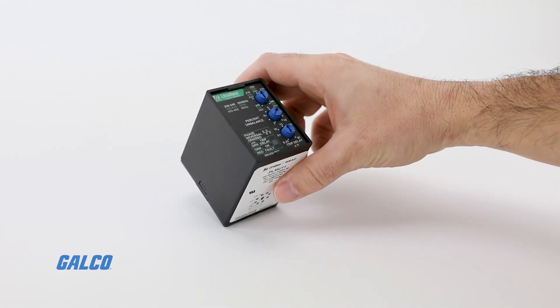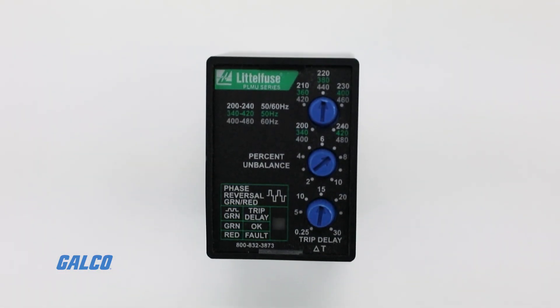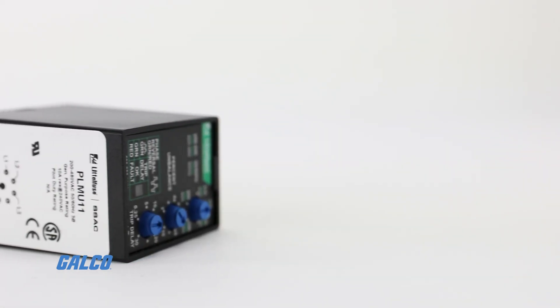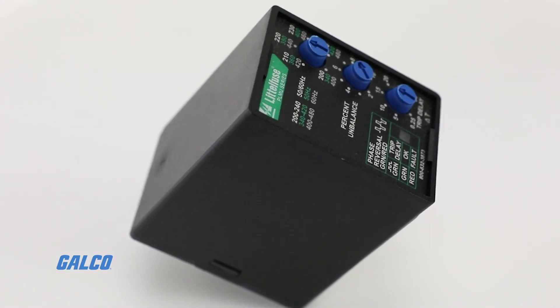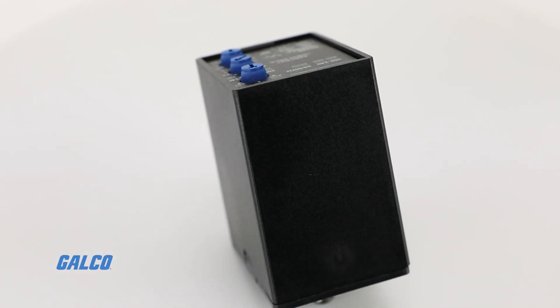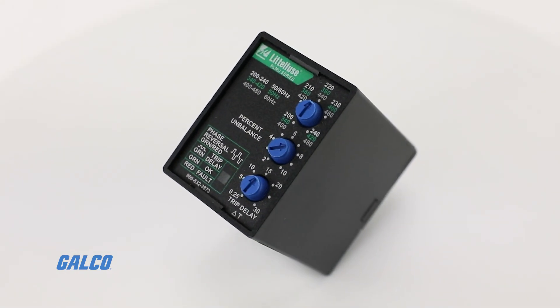The PLMU series by Littelfuse is a voltage monitoring relay that continuously measures the voltage of each of the three phases to provide protection for three-phase motors and sensitive loads. Protection relays are used to automatically operate when one or more phases of the three-phase supply is lost or when the phase sequence is reversed.